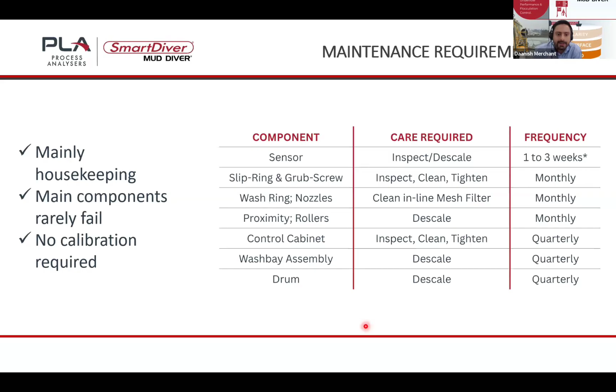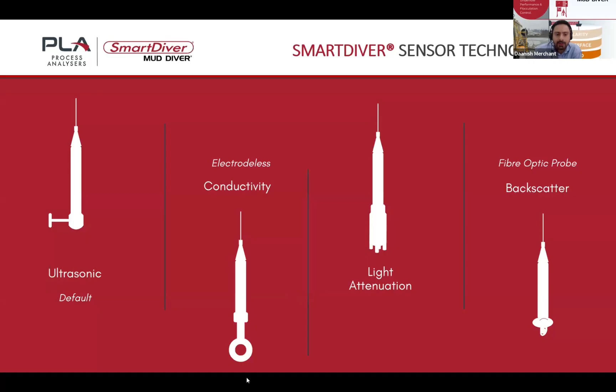We offer 4 different sensor technologies: ultrasonic, conductivity, light attenuation, and fiber optic, depending on the application. But for almost 98% of all applications, we go with the ultrasonic sensor because it suits most applications, mostly due to its higher temperature rating of 106 C. It measures sound attenuation for suspended solids and acoustic impedance for density or specific gravity. The basic principle is that the more solids it registers, the higher the decibel rating or grams per liter rating.